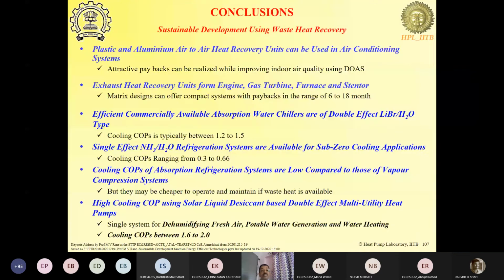So in conclusions, we can say plastic and aluminum air-to-air heat recovery units can be used for air conditioning systems. Attractive paybacks can be realized while improving the indoor quality using dedicated outdoor air systems. Exhaust heat recovery systems from engines and gas turbines, furnaces, tenters can give you payback of 6 to 18 months, depending upon usage, using our matrix heat recovery unit.